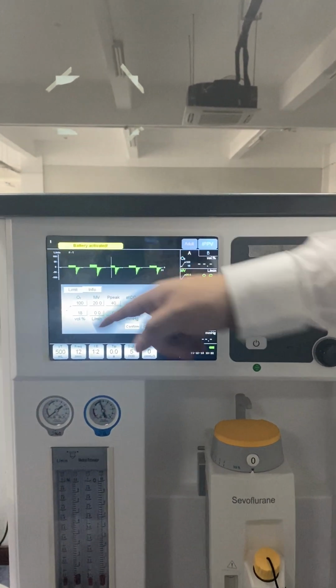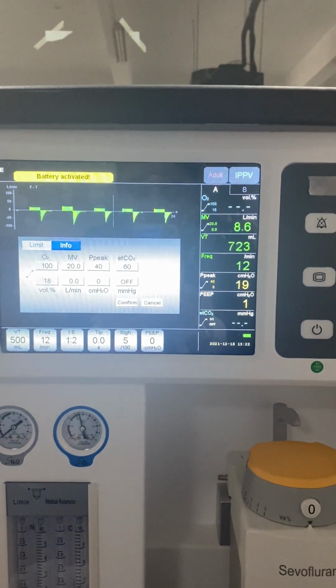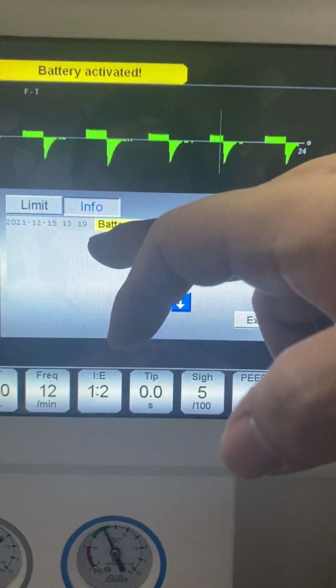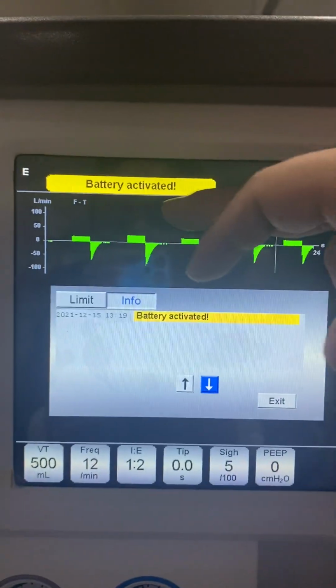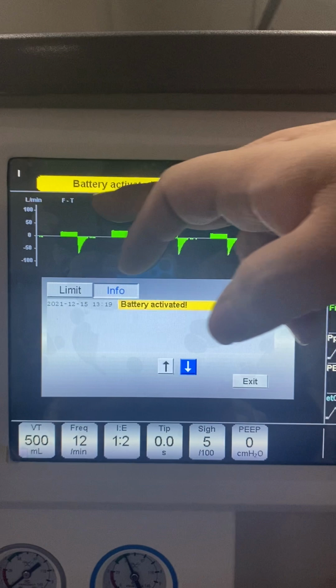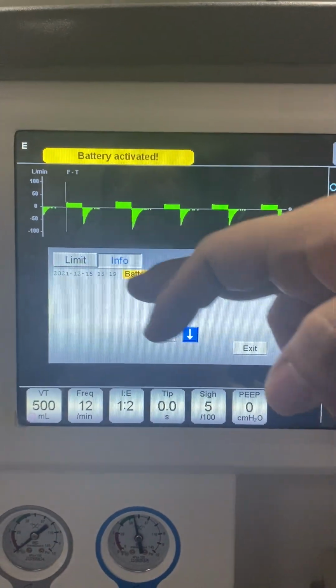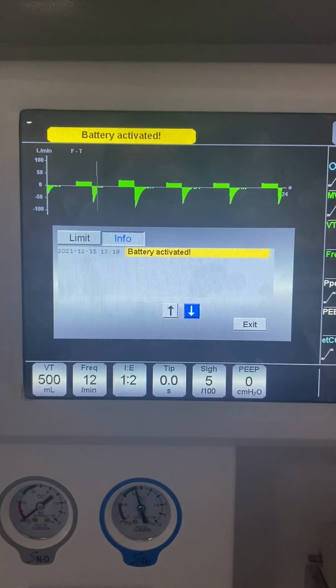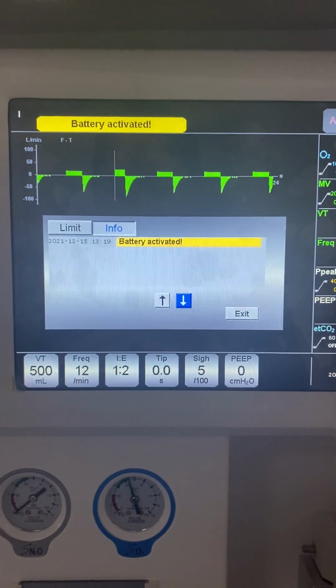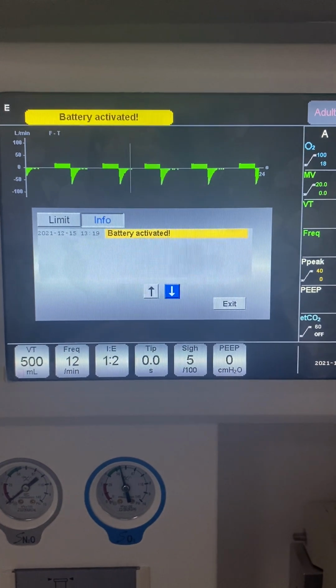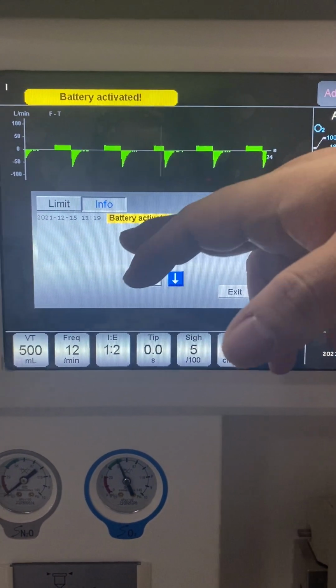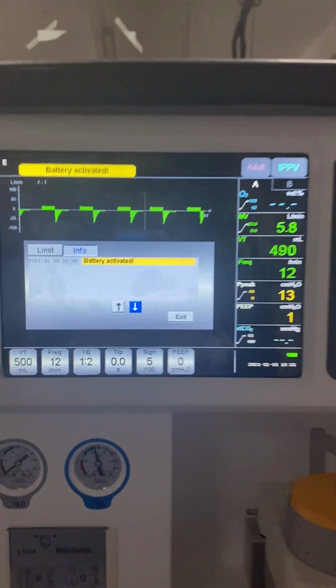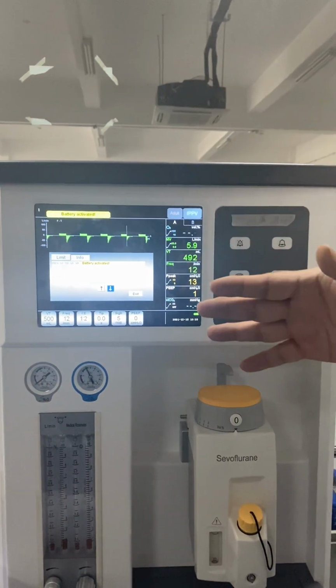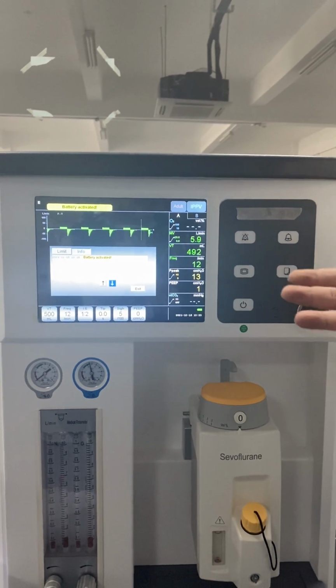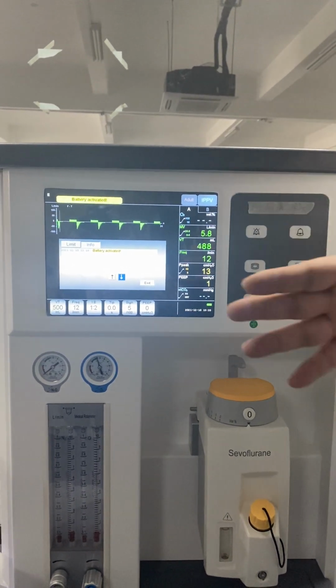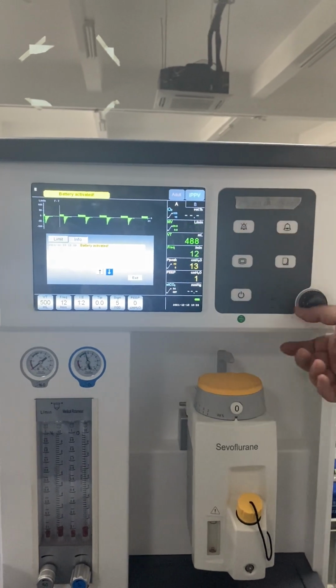And also we can see the second column is for the alarm info. When we change to the alarm info, you can see here it also says battery activated, just the same as here. So all of the alarms shown here will also be shown in the alarm info. The alarm info will show all of the history alarms, even days before, even months before. So after half a year or 1 year, if the engineer comes to do the maintenance, we suggest they check the alarm info on this page. So they will know what has happened to the machine and at what time. They will know what they can do to give the machine better maintenance and to recover the machine to its original condition.